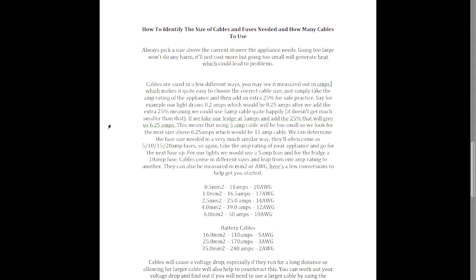Cables are sized in a few different ways, and you may see it measured in amps, which makes it easy to choose the correct cable size. Simply check the amp rating of the appliance, then add an extra 25% to that rating for safe practice, giving you the amp rating you'll need for your cable. For example, if our light draws 0.2 amps, after adding 25% that gives us 0.25 amps.